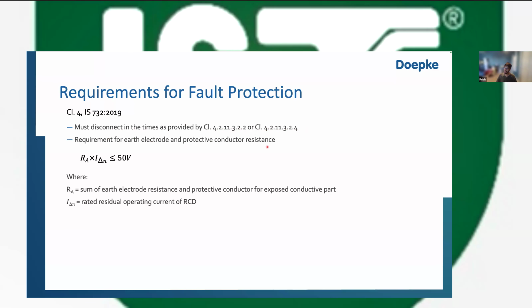Requirements for the earth electrode and protective conductor resistance are such that the resistance of the earth electrode multiplied by the rating of the RCD in milliampere shall be less than or equal to 50 volts. So the sum of the resistance of the earth electrode and protective conductor for that particular equipment, your lift in this case, multiplied by the rated residual operating current of the RCD shall be less than 50 volts. This is the classic equation.